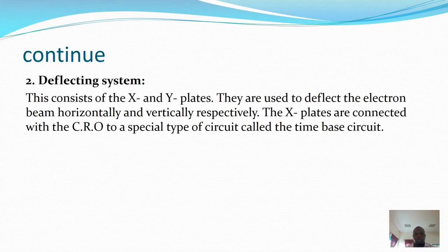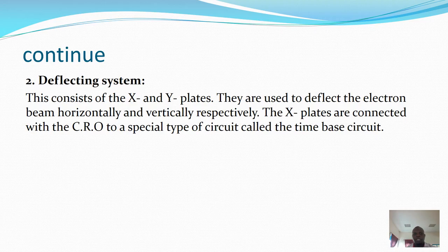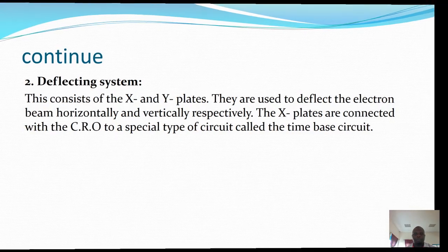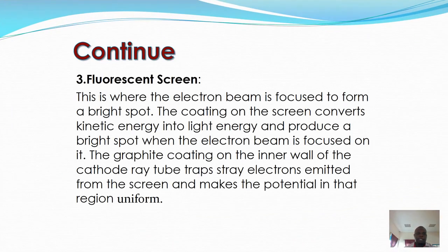The second part of the CRO is the deflecting system. This consists of X and Y plates, which are used to deflect the electron beam horizontally and vertically respectively. The X plates are connected to a special type of circuit called a time base circuit, which is an important component of the deflecting system.